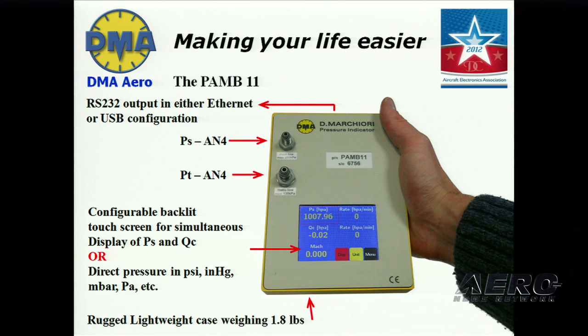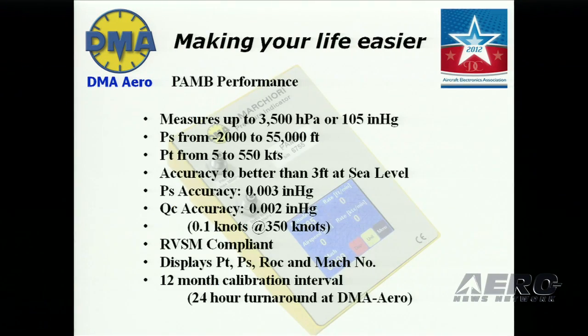The configurable backlit touchscreen can display PT, QC, rate of climb, and Mach simultaneously, or direct pressure in a number of popular units such as PSI, inches of mercury, millibar, pascals. RS-232, Ethernet, or USB outputs are available. It has a measuring range of up to 105 inches of mercury with altitude from -2,000 to 55,000 feet and airspeed from 5 to 550 knots. The standard accuracies can be seen on the slide, and all are equivalent or better than RVSM requirements.